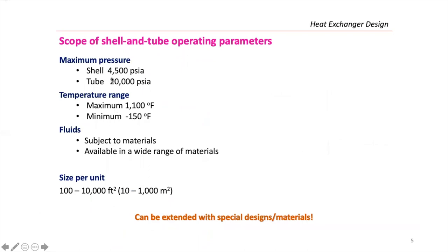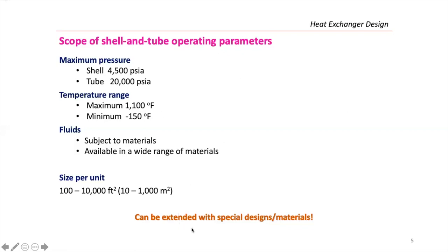Typical operating parameters for shell-and-tube heat exchangers: maximum pressure in the shell around 4,500 psia, tube side up to 20,000 psi. Temperature range from −150°F to 1,100°F. A wide variety of fluids can be used, with material selection depending on the fluid type. Unit sizes range up to 1,000 m². These parameters can be extended with special designs and materials — this is just to give you an idea.